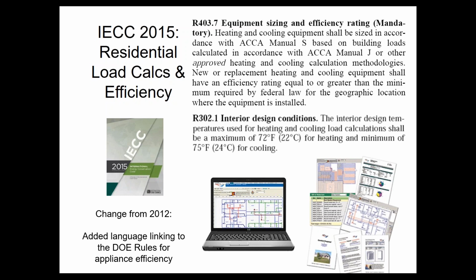One other big change to this section, which seems kind of quirky, is that they added this language at the bottom of 403.7 that you have to install equipment that meets the efficiency rating of the minimum federal law. Prior to that, it didn't say that. So what that meant is if I could get my hands on a 10-SEER air conditioner, I could install it residentially. There's nothing in the energy code that said I had to have a certain efficiency of equipment. Kind of weird. So now the language is in there. So if in inventory I have a 10-SEER air conditioner, I cannot legally install that air conditioner in a place that's following this code. Right? So they've kind of tied up that little loophole there.